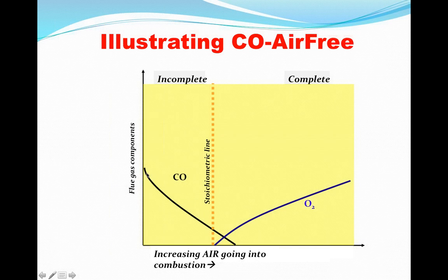The CO line: CO production drops as you increase the amount of available air to mix with the fuel, so that the carbon in the fuel can join with the oxygen, and you want to create CO2. That's the true objective of combustion, to create maximum CO2. That's maximum energy efficiency. But if you don't have enough oxygen around, you only get it to CO, not all the way to CO2. Those levels will drop as you provide more and more oxygen in the combustion system. And in the real world, you do get a little bit of CO coming past the line of perfect chemical balance, the stoichiometric line.